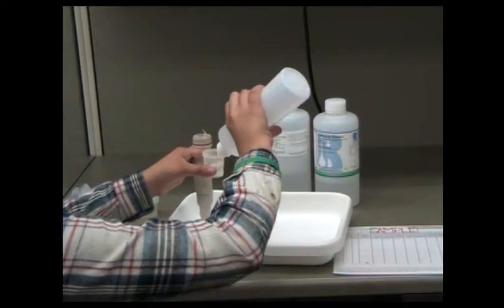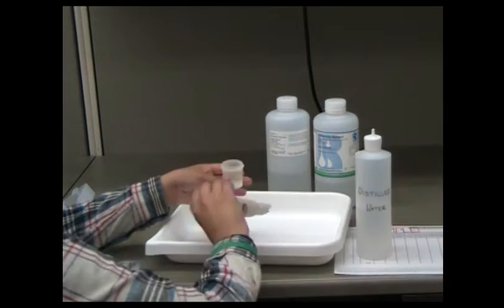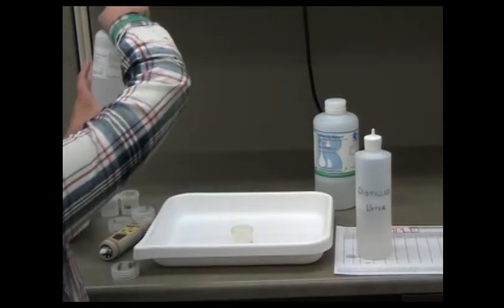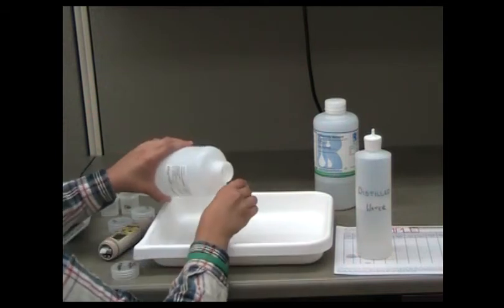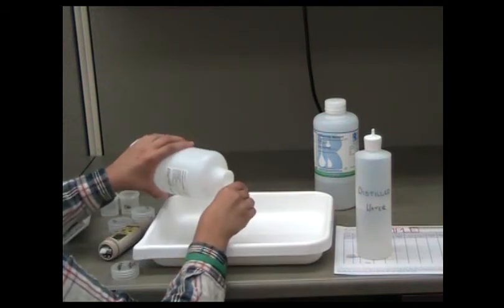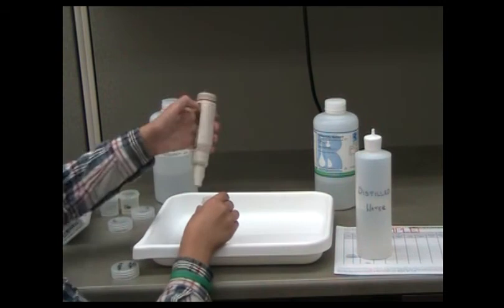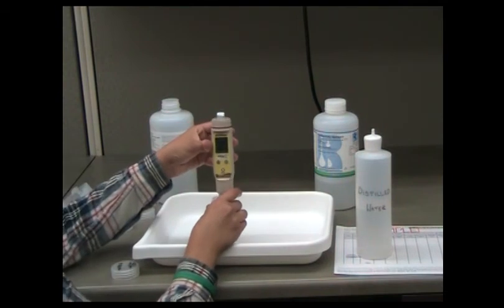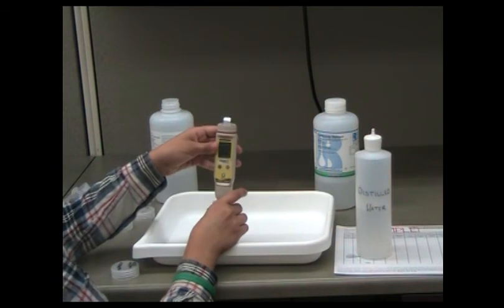Rinse the probe three times with distilled water. Repeat the calibration process with the low standard 1,413 microsiemens per centimeter. If the calibrated specific conductance for this standard is outside the range of 1,366 to 1,460 microsiemens per centimeter, please recalibrate the meter.